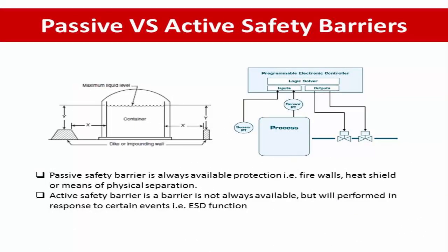Next: passive and active safety barriers. A passive safety barrier is one whose safety function is always available as an inherent property. Examples include a firewall, heat shield, or means of physical separation such as a fence. An active safety barrier is one that is not always available but will be activated upon certain events. For example, an emergency shutdown system (ESD) in a process plant is an active safety barrier which will be activated when a hazardous situation occurs.